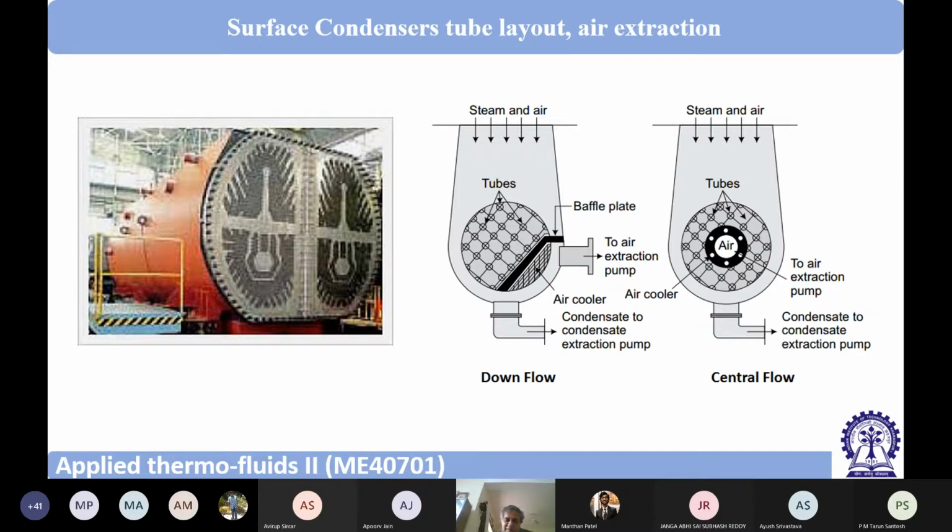It will condense whatever water vapor is there, which means it will make a good separation between air and water. And at that portion, we can have some sort of opening and join our vacuum pump, and mostly air is there, water has been condensed due to the high rate of heat transfer, and we can take away the air.